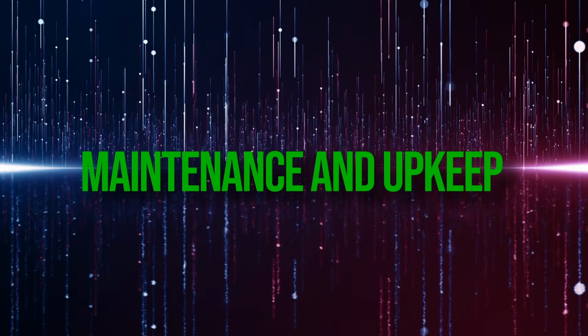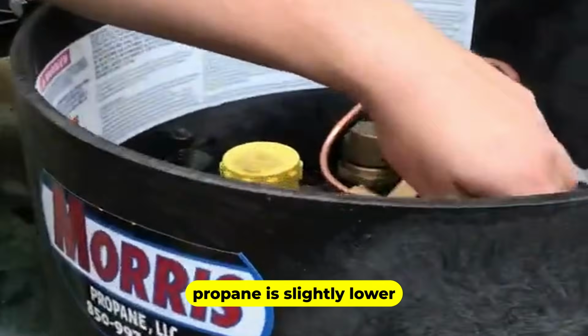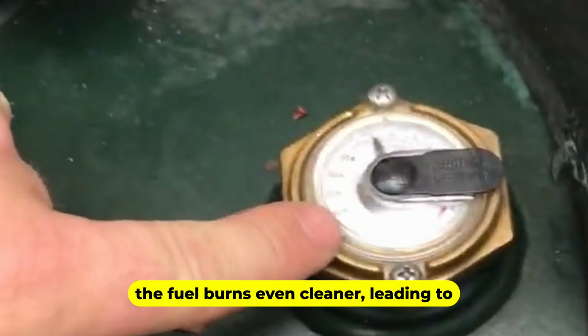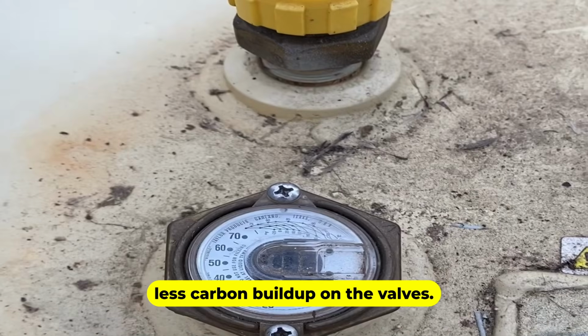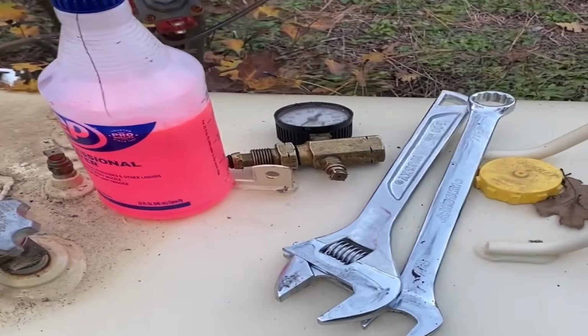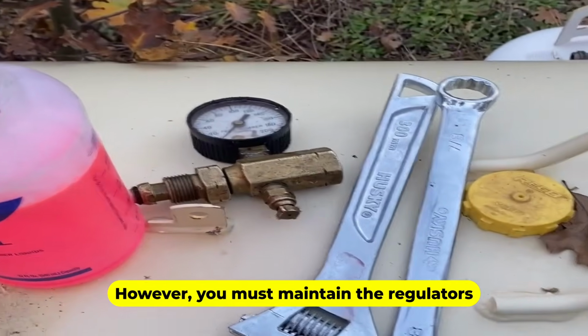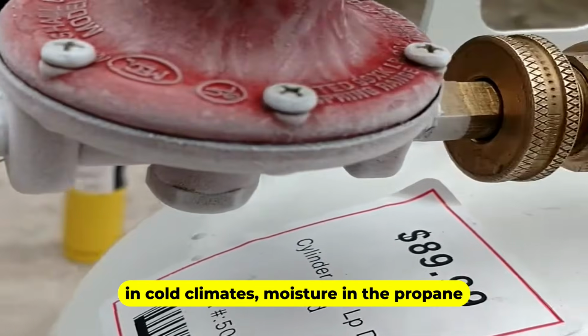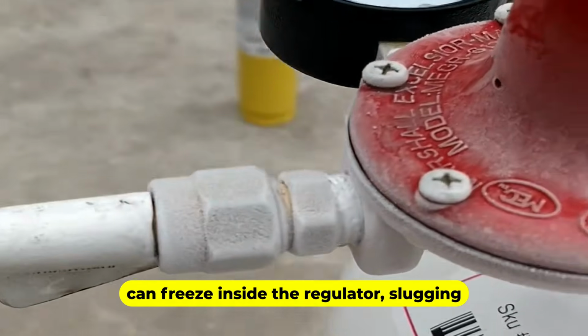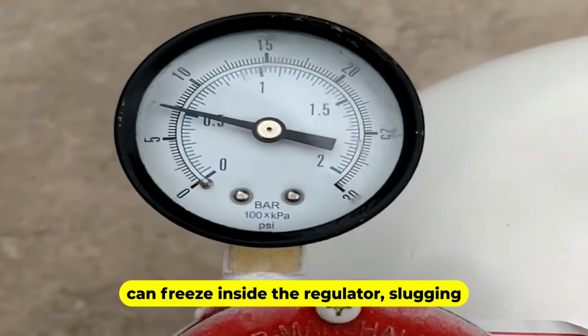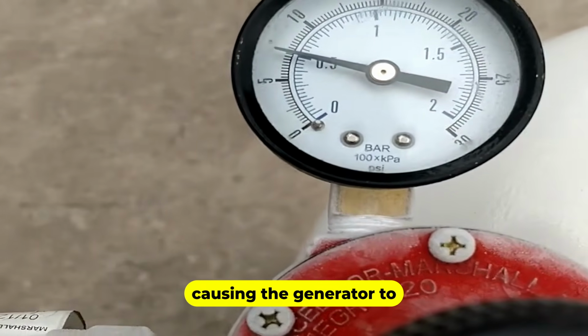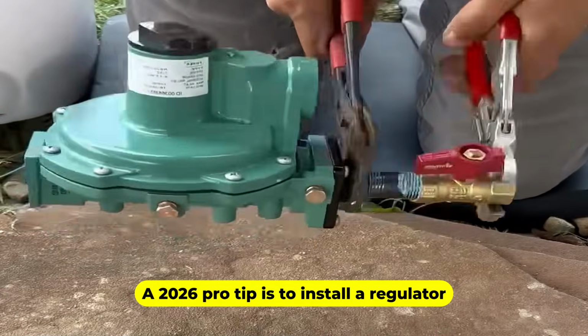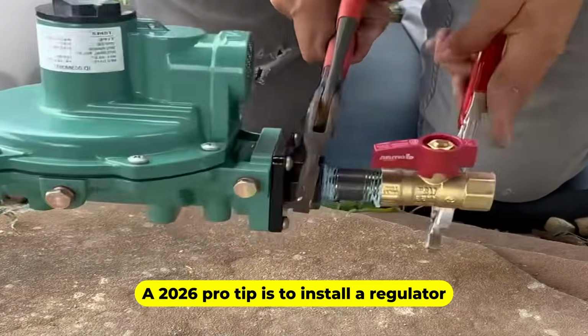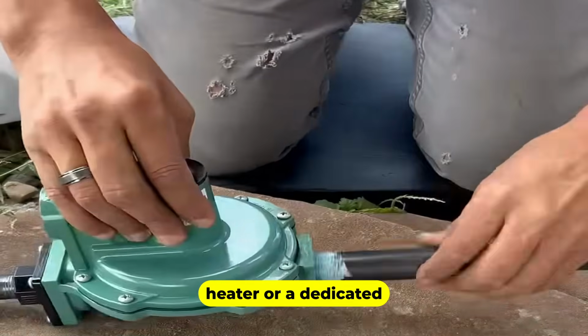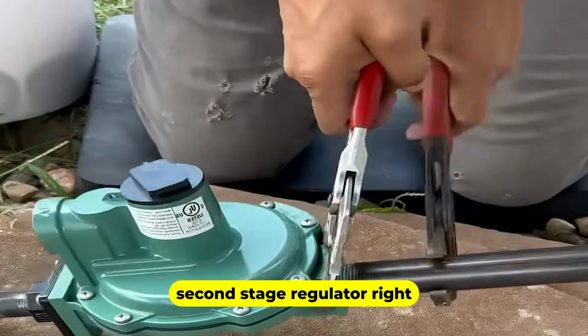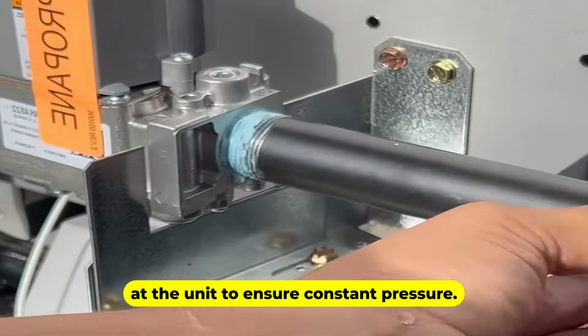Maintenance and upkeep. Maintenance for propane is slightly lower than natural gas because the fuel burns even cleaner, leading to less carbon buildup on the valves. However, you must maintain the regulators. In cold climates, moisture in the propane can freeze inside the regulator, slugging the fuel flow and causing the generator to stall. A 2026 pro tip is to install a regulator heater or a dedicated second stage regulator right at the unit to ensure constant pressure.